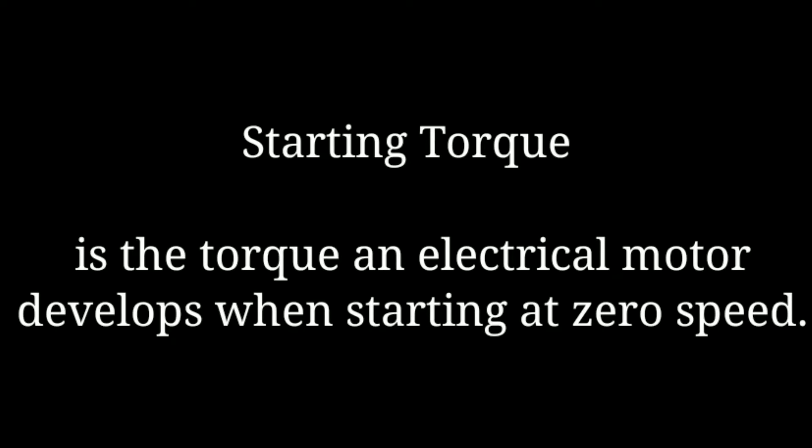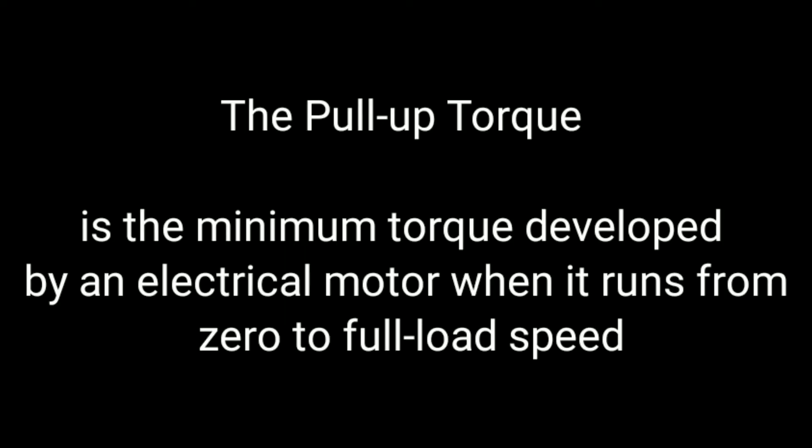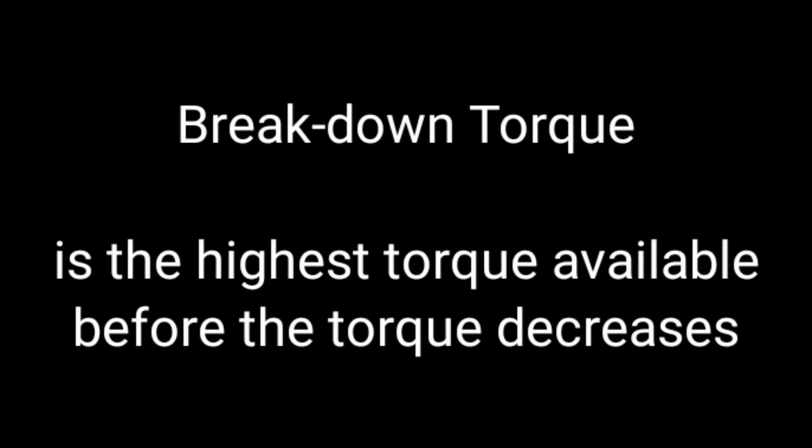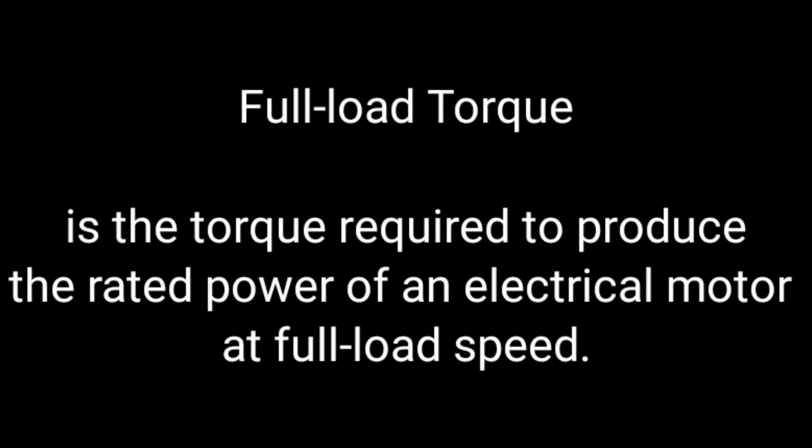There are different types of torque. First, starting torque is the torque an electrical motor develops when starting at zero speed. Second, pull-up torque is the minimum torque developed by an electrical motor when running from zero to full-load speed. Third, breakdown torque is the highest torque available before the torque decreases.